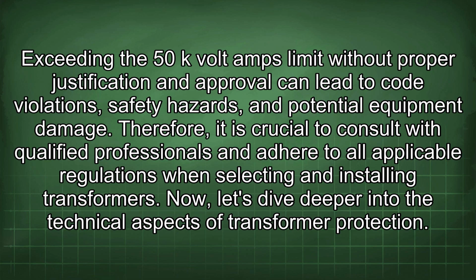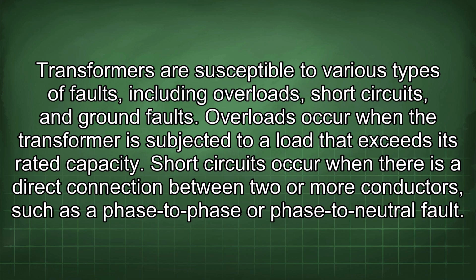Exceeding the 50 kVA limit without proper justification and approval can lead to code violations, safety hazards, and potential equipment damage. Therefore, it is crucial to consult with qualified professionals and adhere to all applicable regulations when selecting and installing transformers. Now let's dive deeper into the technical aspects of transformer protection. Transformers are susceptible to various types of faults, including overloads, short circuits, and ground faults. Overloads occur when the transformer is subjected to a load that exceeds its rated capacity.